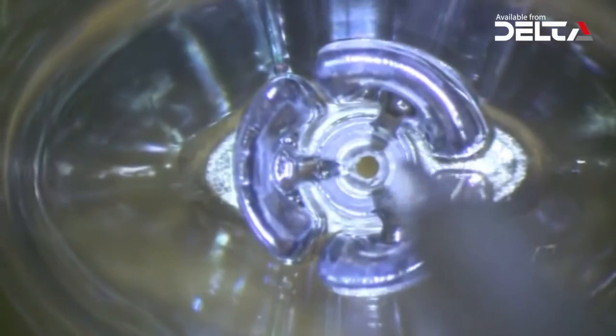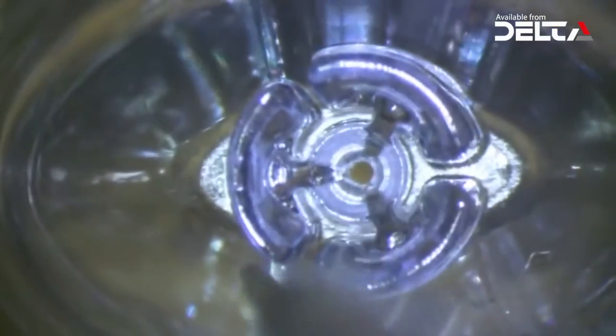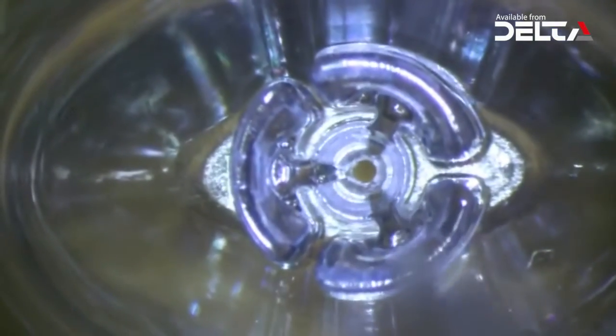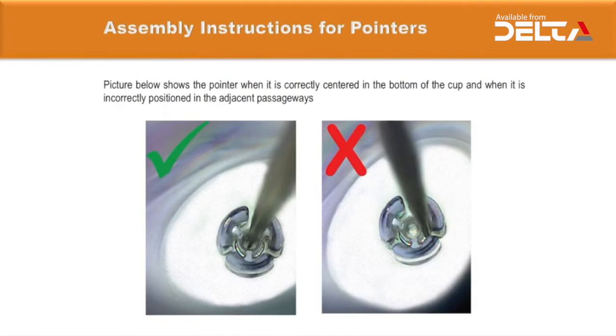During the centering process, the pointer tip may not be exactly located at the center of the cup. This is very important for navigational success, so it is critical to verify visually that the tip of the pointer is perfectly centered in the middle of the cup at the bottom of the tip of the introducer.